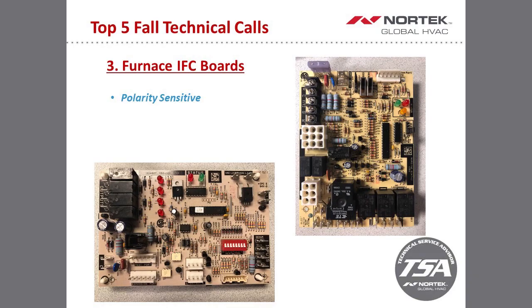The furnace needs to have a proper ground, meaning that if you end up using a copper pipe that's, say, adjacent to the furnace, the copper pipe has to be copper all the way to the street. If it transitions to PEX or galvanized before it goes out to the street, that to us is not a sufficient ground. When checking the grounding of the furnace, you want to measure your ground wire and your neutral wire, and you should read 0 under a normal circumstance. You're allowed up to half a volt.